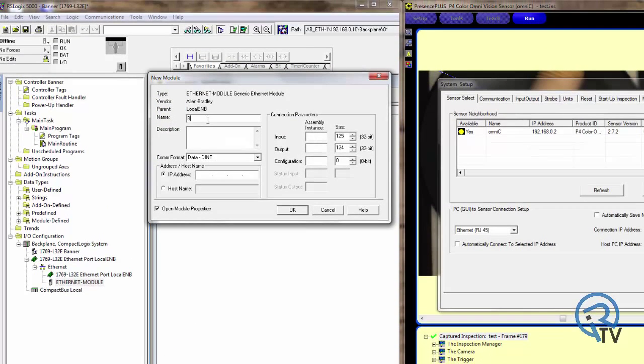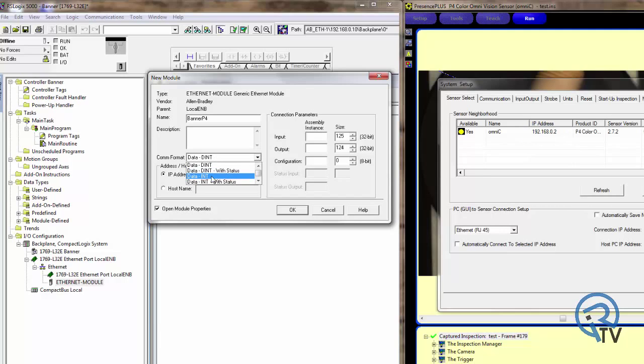First thing, give it a name. I'm going to assign Banner P4. For IP address, enter in the target IP address of 192.168.0.2. In COM format, I like to choose Data Integers, so they come back in 16-bit integers.